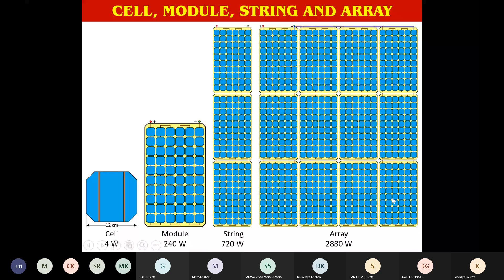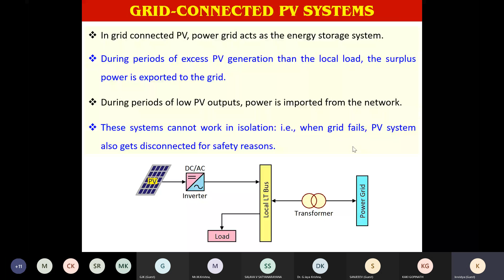Now, grid connection of the PV system, because you can have a standalone PV system, you can also have a grid connected PV system. And since the output of the PV system is DC, you need a DC to AC conversion mechanism. So depending upon the number of modules connected, you can have different types of inverters. Normally, inverters are currently available for voltage levels of 800 volt, 1000 volt, and up to 1.5 kV, that is 1500 volt DC. For getting that much voltage, because a typical 72 cell module output voltage will be around 36, whereas your inverter is 1 kV, you can connect many modules in series to get 80% of that 1 kV, that is say 800 volt. So you can connect about 18 to 19 or 20 modules in series in a string.